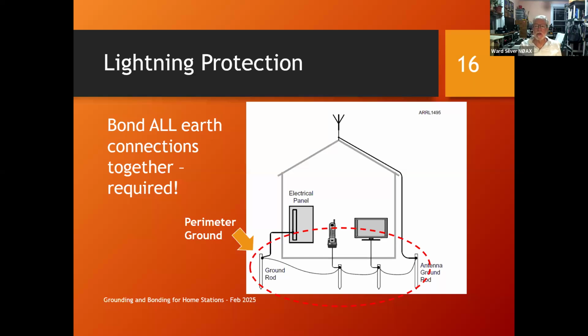Why is that? Because the ground systems, the ground electrodes, were not bonded together. And so when the lightning flowed through the dirt, it created this really high voltage between point A and point B. And high voltage between point A and point B causes current to flow. And the current is what does the damage. So your perimeter ground system is a bunch of ground rods all tied together with a heavy conductor. And everything is tied to that outside.